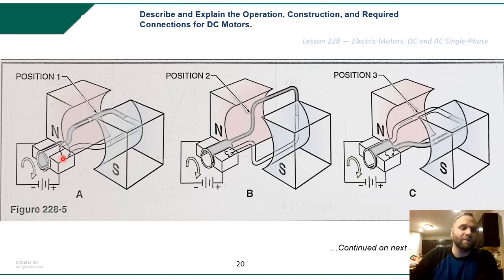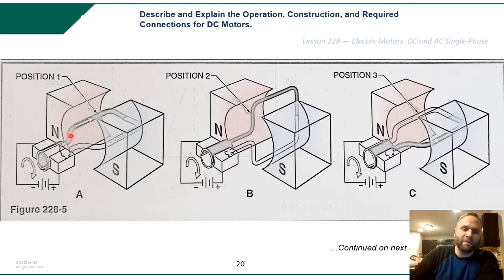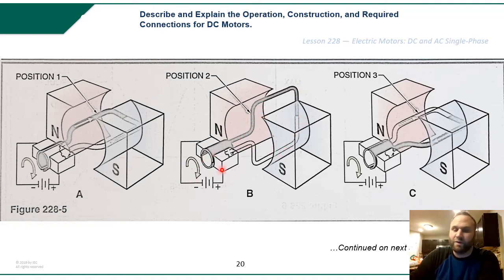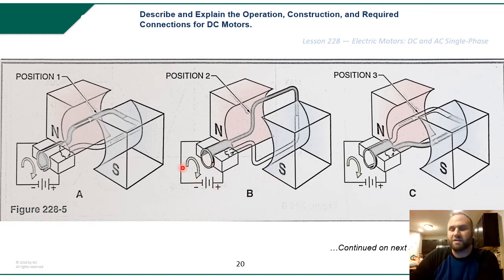As shown in this drawing, you can see there's a split here — this would be your commutator ring. Current is flowing in this direction and it's in position one, which provides quite a bit of torque, forcing the armature to rotate. When it's in position two, the armature is receiving very little to no torque at all and is solely running on its own momentum. If we did not split the direction of electron flow through the loop, this armature would come to rest. But because we split the direction of electron flow, the armature is allowed to continue to rotate.